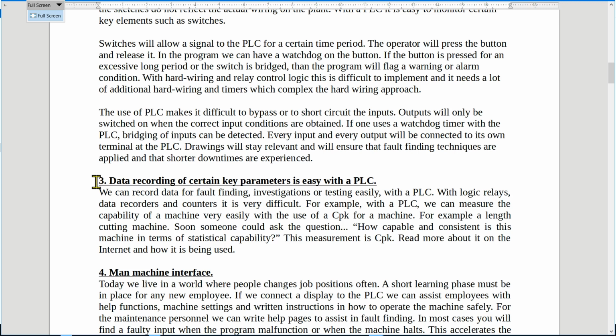Point 3, data recording of certain key parameters is easy with a PLC. And the question has always been asked, at what speed is the conveyor running? What was the output yesterday? What was the output today? With normal conventional relay logic, what we call the clickety-clack panel, it is not possible. But with PLCs, we can record data for fault finding, investigations, or testing easily. With logic relays, data recorders, and counters, it is very difficult to do with hardwired panels.